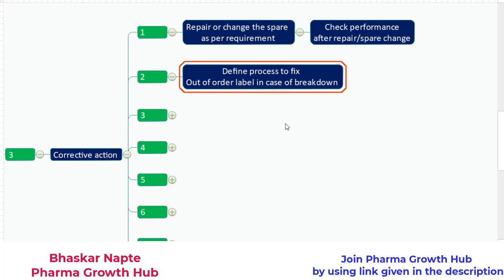The question must come to your mind: why did the analyst use a faulty sonicator? If there is no information available to the analyst that this sonicator is not performing well, then it is not the fault of the analyst but the fault of the system. To give information to the analyst about whether the instrument is working well, you can put a label — for example, 'out of order' — if the instrument is not performing well or is under breakdown. The third corrective action is to define the preventive maintenance schedule for the sonicator if not already available.